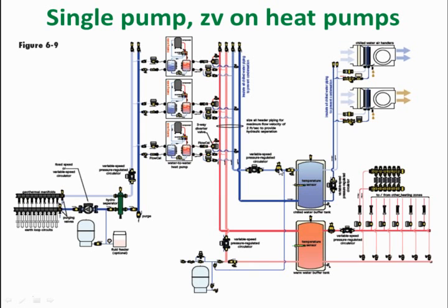This side we put a Discal on the input side to this tank. On this one here, since it's hot water, we put that on the output side, because you want to get your air removed at the highest temperature in the system. Certainly in the heating system, that's going to be the hottest temperature point there. On this system here, you've got cold water coming in here, warmer water going there. That's going to be a little bit better spot to remove the air on that. So that's, I think, some of the changes as we go through these drawings here.